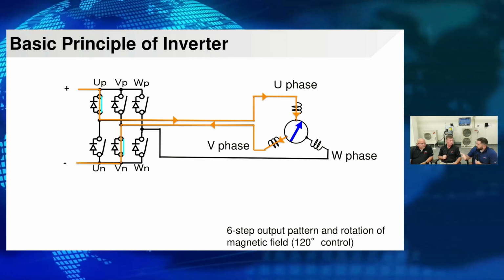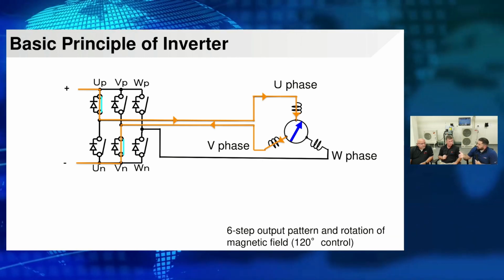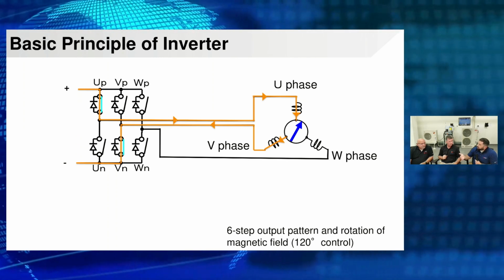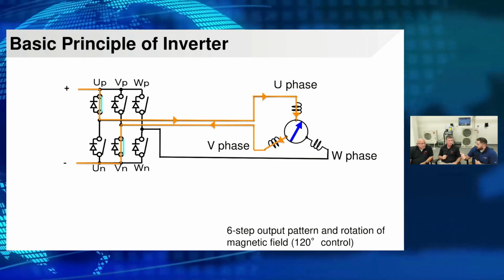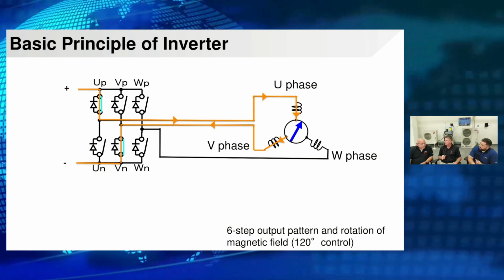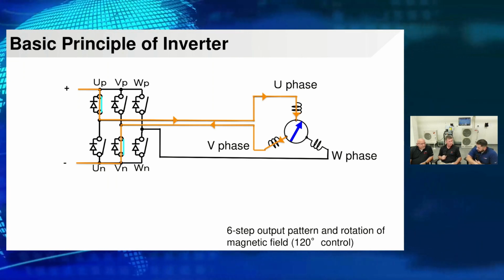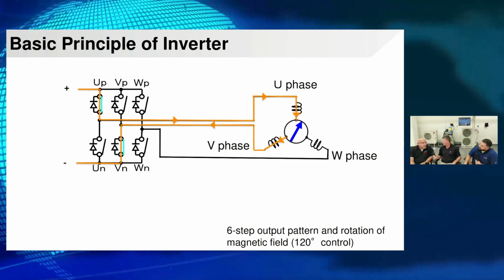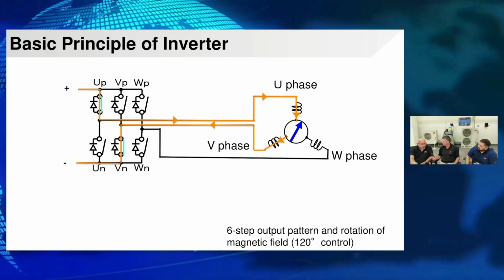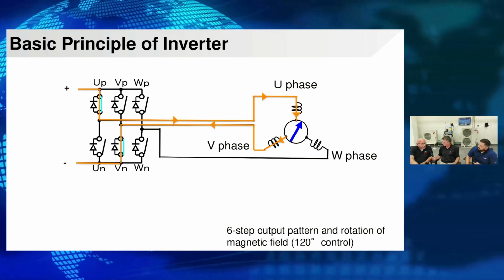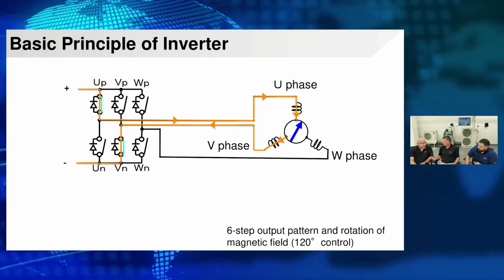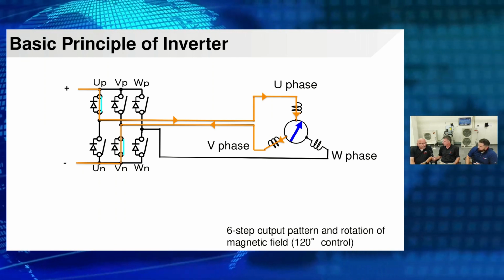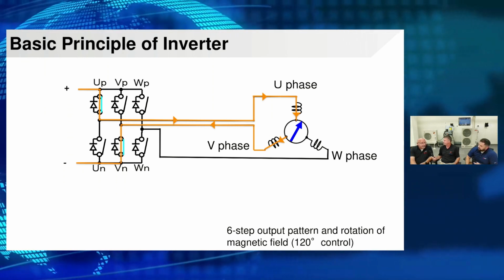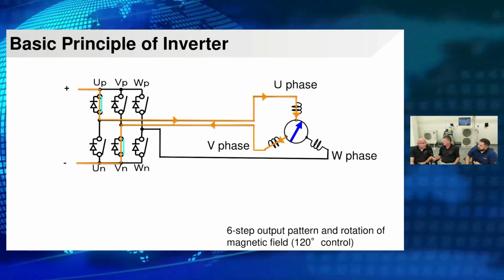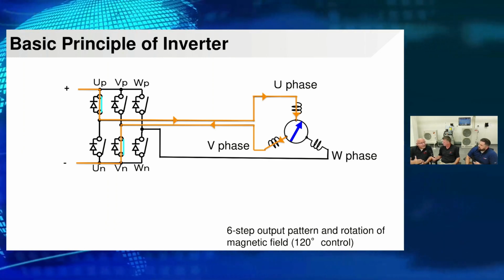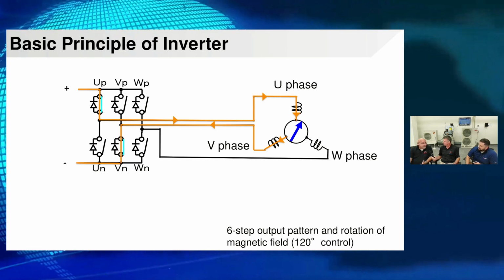Because no matter what our incoming voltage is, it's always going to be in relation to what our DC voltage is coming out of that converter stack. And so the high voltage DC is what can take out boards. So we do want to make sure we check our incoming voltage, because it can affect the entire inverter circuit. Another beauty of the inverter is that on those occasions when we have high incoming voltage, the inverter will see it and actually ramp the compressor down. It'll keep it running, but ramp it down, so the customer will not get full capacity cooling. So they'll call the contractor and say, my system is not cooling.